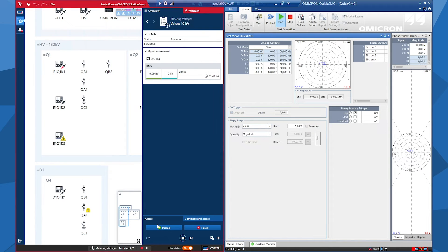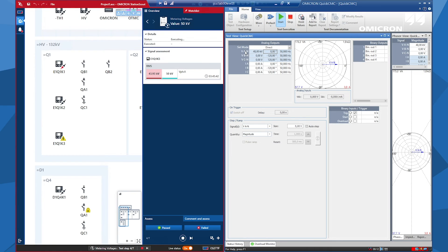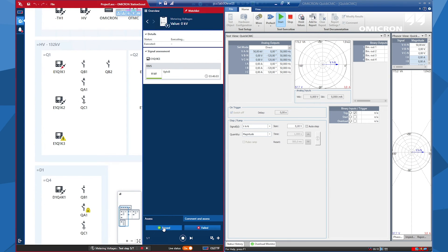I click pass, because I see in the data model 9.99 kV — that's okay. Now here comes 100 kV. I click on 100 and we are still in the margin, so this test case is evaluated as green. I click pass. Now in this step, I will make a failed condition demonstration. For that, I will inject some 44 kV, and as you see it's red here. As soon as I inject a value outside the 5% tolerance of the expected value, it will turn red. But the real value expected to be seen by the IED is 50 kV, so that's okay for me. This can go on for phase B — I'm not injecting anything from phase B, and in the next step I will also inject 100 kV from phase B.